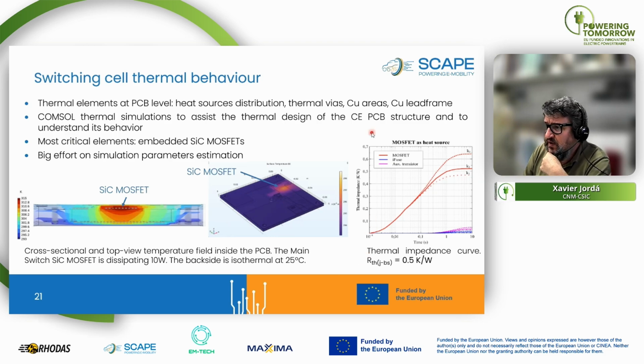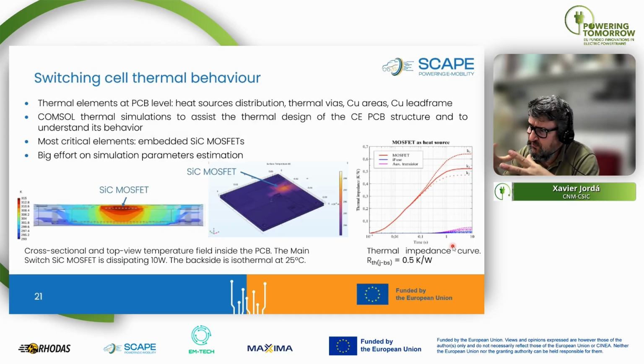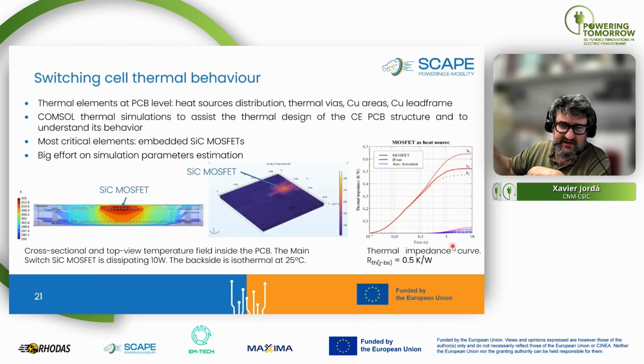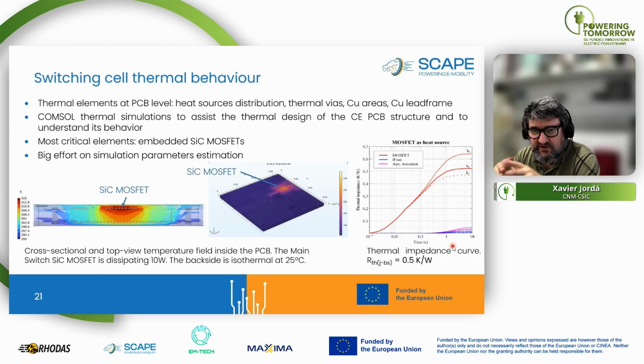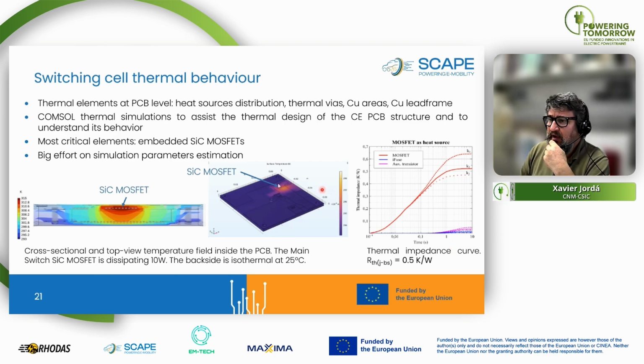As a characteristic figure describing the thermal performance of the switching cell, we simulated the thermal resistance, or complete thermal impedance in dynamic mode, or thermal resistance in static mode, between the junction temperature of the embedded silicon carbide MOSFET and the backside temperature. During the design phase, we achieved values around 0.5 Kelvin per watt, which is an acceptable figure.